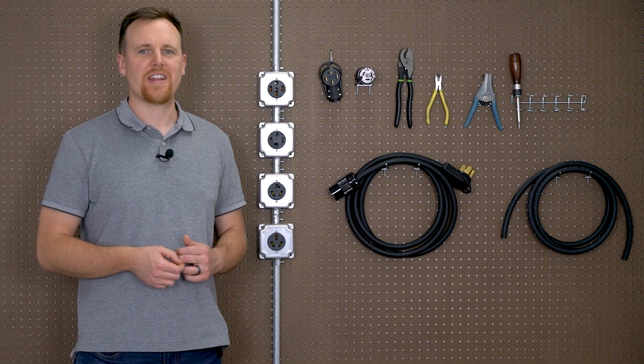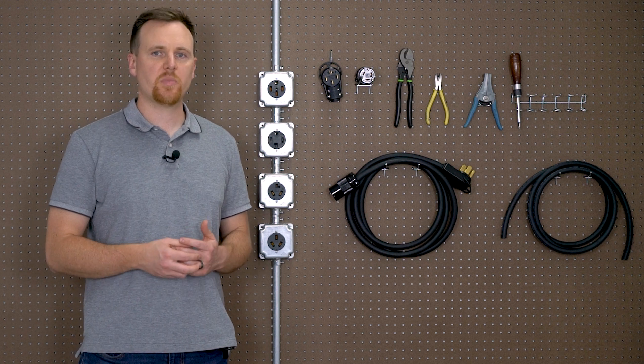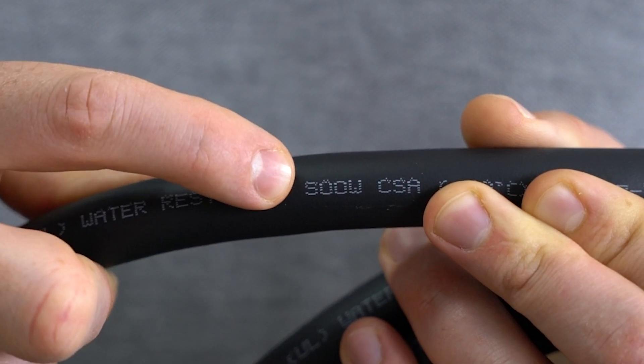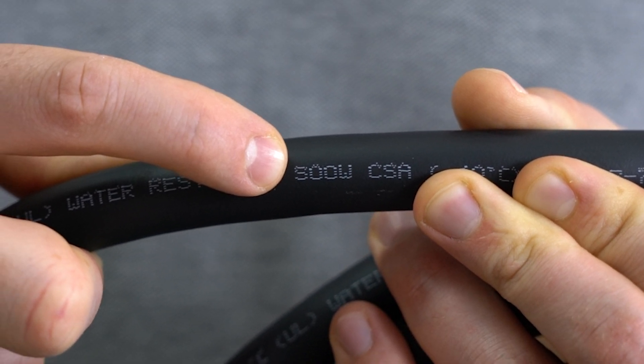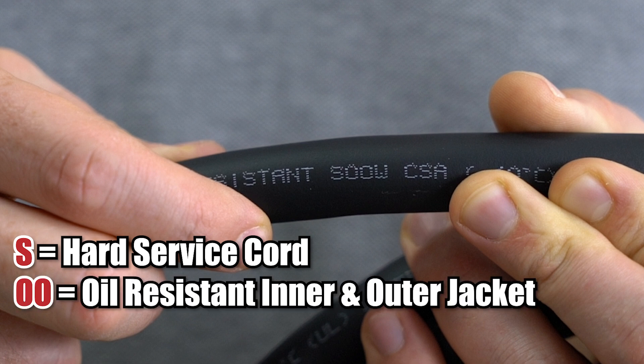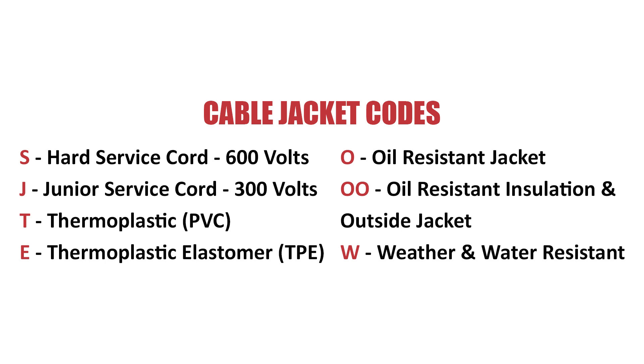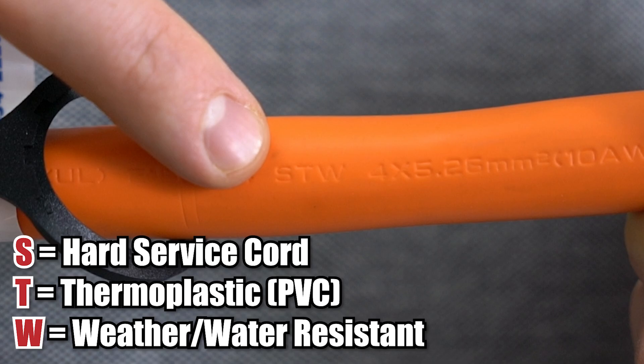Now that we have the wire gauge narrowed down, we can pick the cable jacket. If you want ultimate flexibility and maximum protection against oil and weather, the best fit would be a SOOW rubber cable jacket. The S stands for hard service cord with a 600-volt rating, double-O represents oil-resistant insulation and outer jacket, and W means weather and water resistant. If you want something cheaper but still flexible and durable, you could use an STW cable jacket made of PVC, which also has a 600-volt rating.